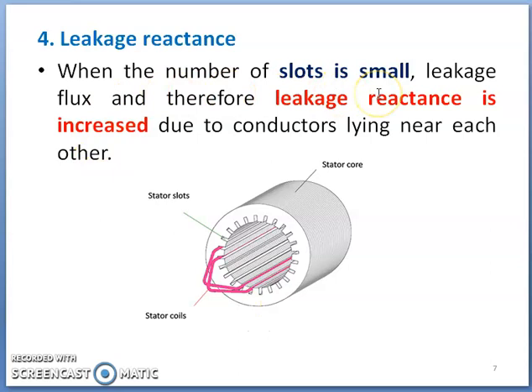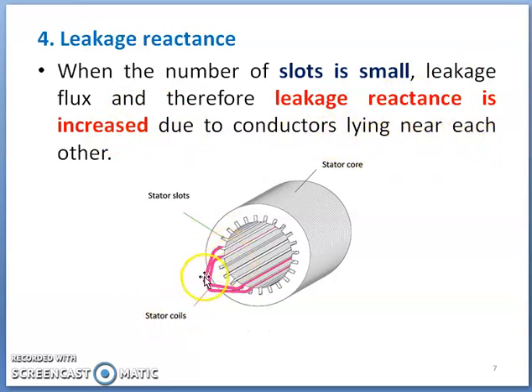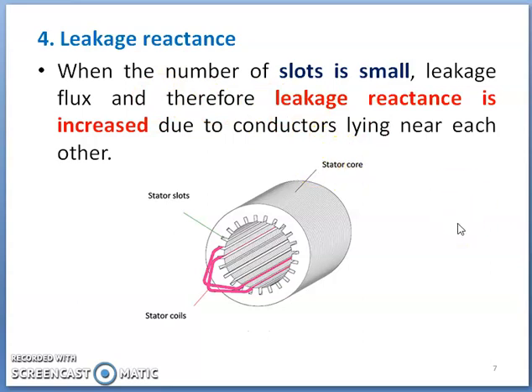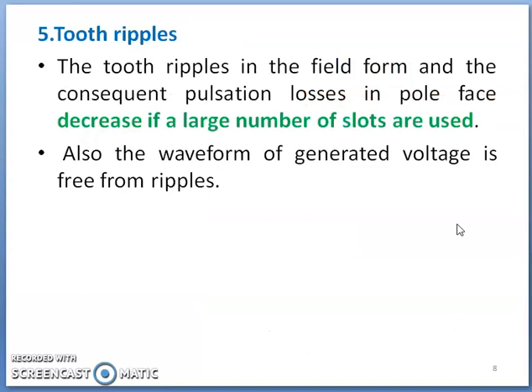Regarding leakage reactance, when the number of slots is small, there will be an increase in leakage flux and consequently leakage reactance increases. This is because conductors come very close to each other. The image shows stator coils placed in the slot, and with a smaller number of slots, two conductors come close, increasing leakage reactance and affecting some performance parameters of the machine.